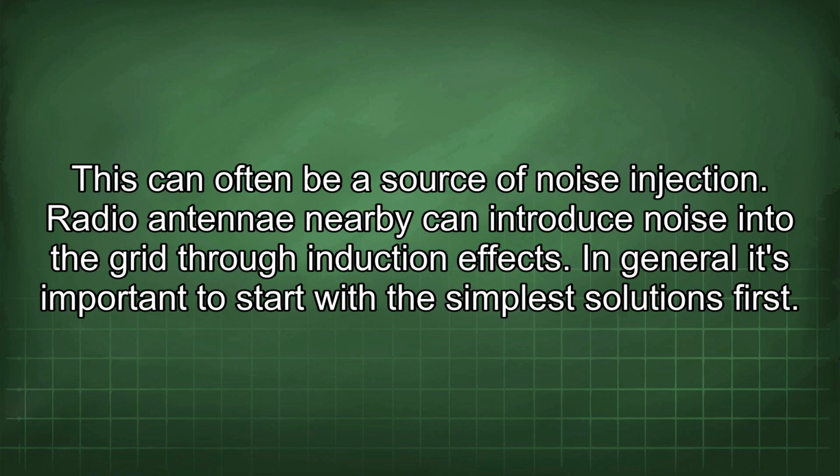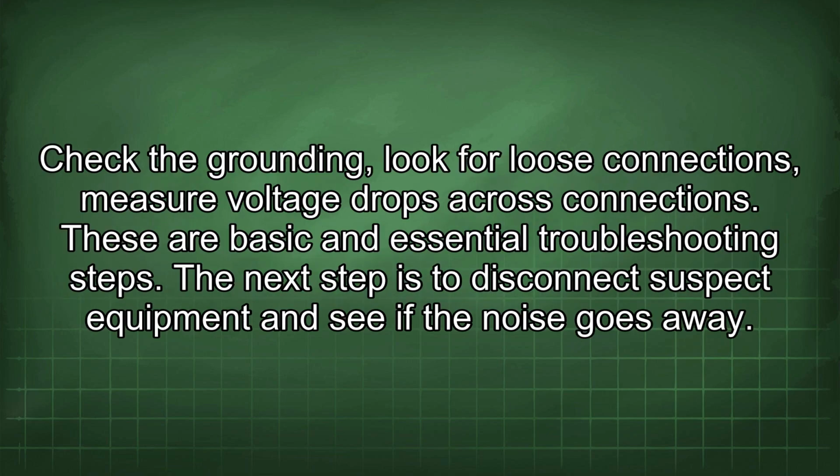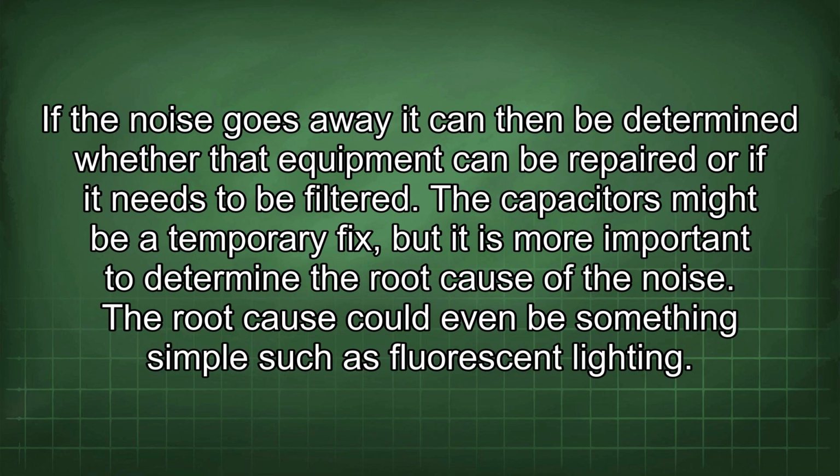In general, it's important to start with the simplest solutions first. Check the grounding. Look for loose connections, measure voltage drops across connections. These are basic and essential troubleshooting steps. The next step is to disconnect suspect equipment and see if the noise goes away.